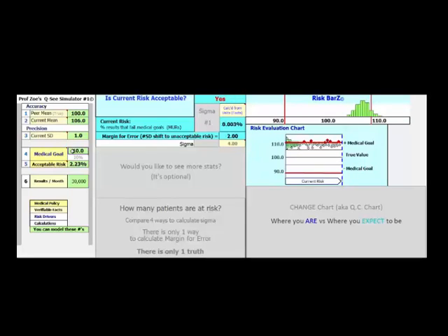We're going to go back to the easy way. We'll set it back to the CLIA limits. But now I'm going to come down here and I'm going to say, I'm going back up to 10. Well, no, let's bring the SD up this time. That looks like more fun. I'm going to increase my standard deviation to 1.5. Now, if I believe that the acceptable risk level should only be 0.1%, this method is unacceptable.